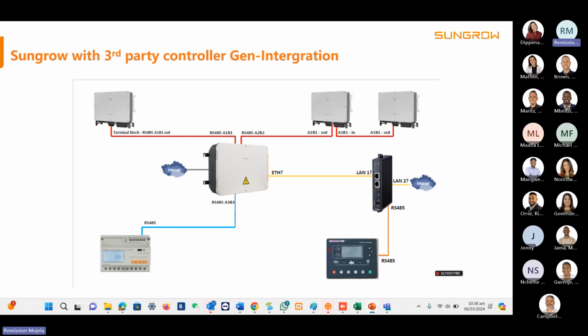But so far, the one that has been tested with the Logger 1000, the box that you see there, is called the COM100E. It has the Logger 1000 built inside. Basically, it's just a box that powers up the Logger 1000. So you can see that the RS485 communications goes directly into the Logger 1000. The RS485 communications from the inverters goes directly into the COM100.